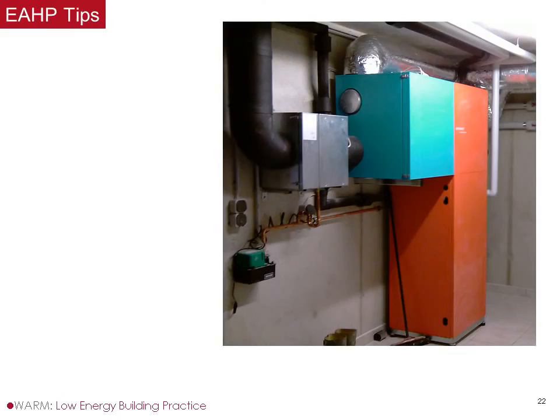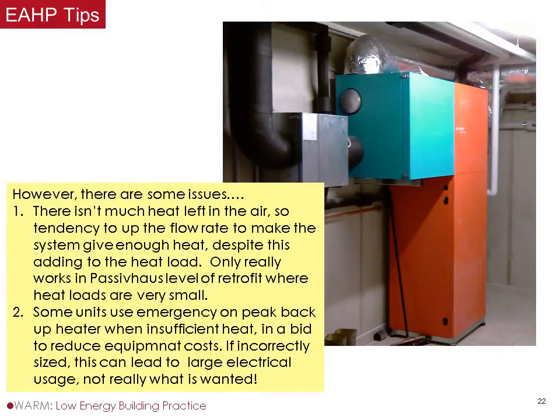However, there are some issues. Here's a picture of one: the green bit is the MVHR, and the red bit is the heat pump with a hot water cylinder in the bottom half. The issue is that there isn't a lot of heat left in the air, so there's an awful tendency for manufacturers to increase the airflow rate through the building so you can get more heat. But if you think about that, it's mad, because you're eating your own tail - you've increased the heat load just so you can recover more heat from it. Silly. You really need to be very well insulated before considering using these, I'd suggest.